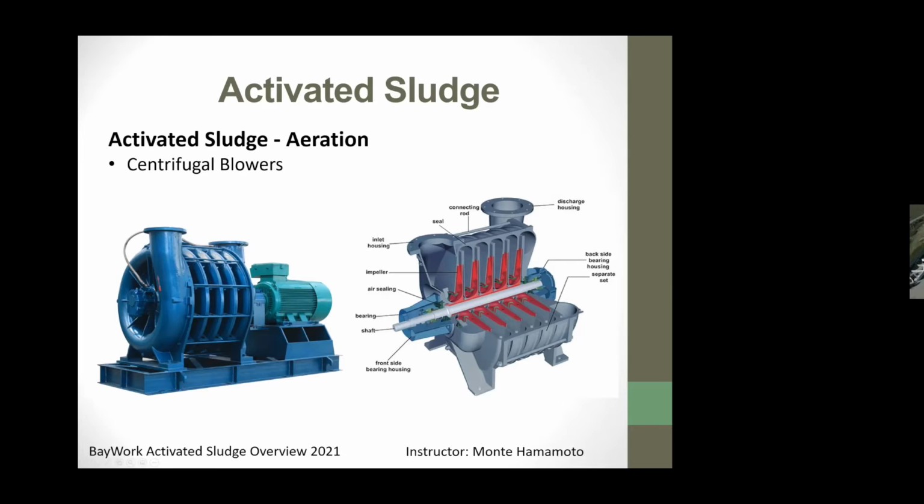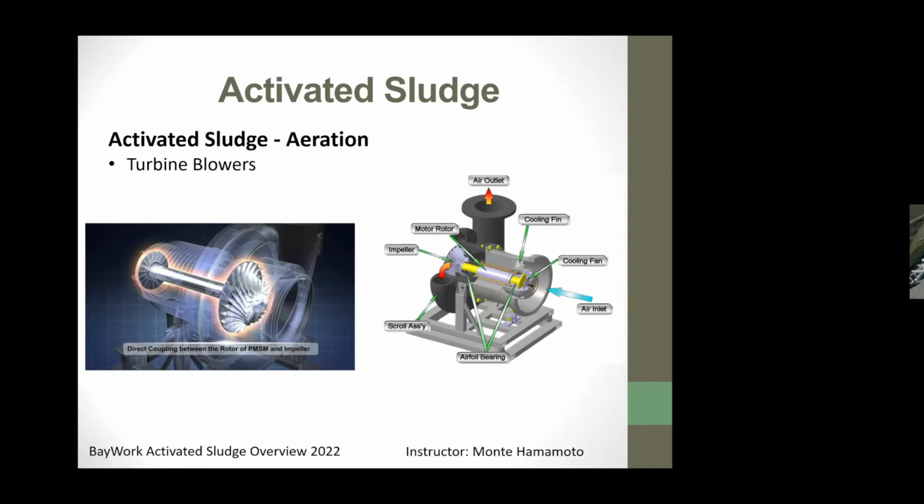Where if you then, like we have, go to these microturbines, these turbine blowers are much more efficient. There's a lot less friction loss. There's a lot less drag. You can put them on variable frequency, changing the speed of the blowers themselves to match whatever your need is at that time of the activated sludge, because depending on the time of day, your flows come up and down. Your air requirement's going to also kind of go with that flow. So we're able to control things better. Efficiency wise, it saved us a bunch of money also.